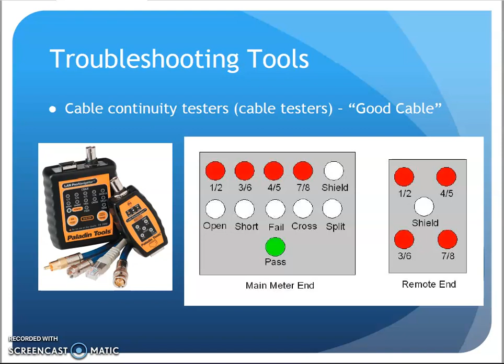If I have a problem, though, most of these have some kind of button to look for a fault. This one actually has a fault check that lets me go through each wire pair individually. So I test and it comes up fail. If I start pushing that fault check button, it goes through each pair individually, and it'll come up with, hey, pair 4-5, we have an open—there's a break in it.